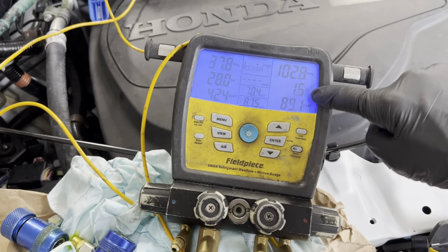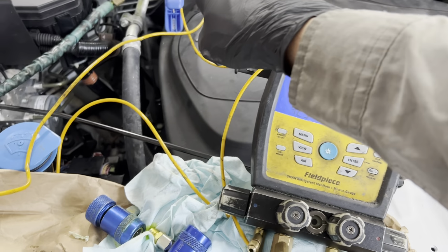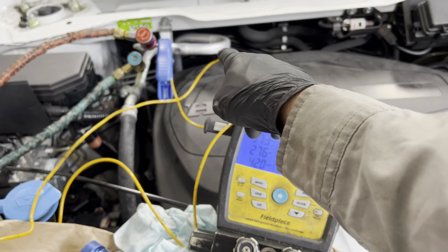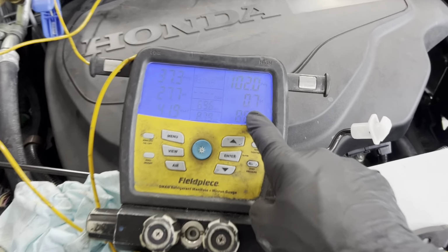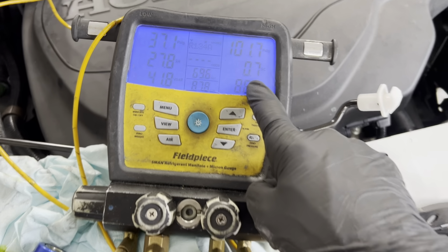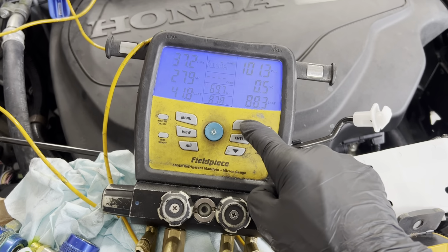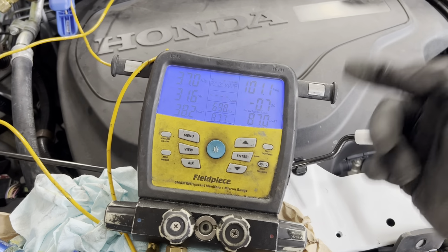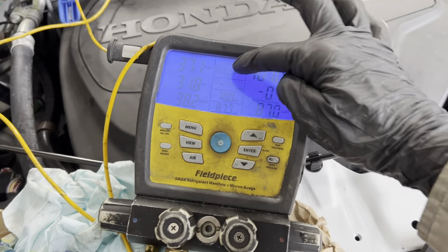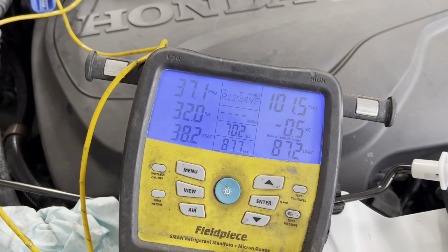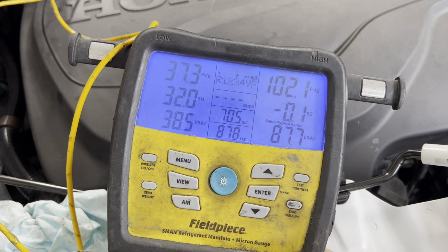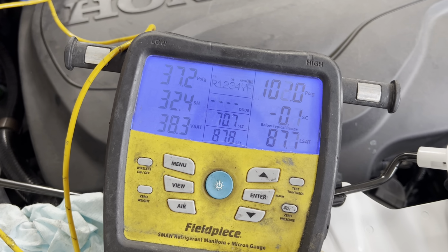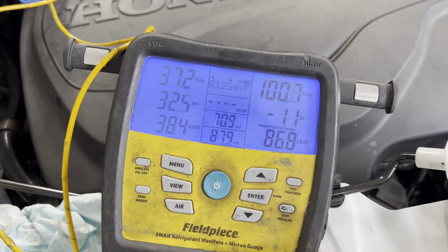Look at what our subcooling is. At that point, that's where it enters out of the condenser right here. So by the time it gets to the internal heat exchanger, look at where our subcooling is. Oh, yeah, idiot. Okay, now look at where our subcooling is. Now we got the right gas. It was on 134. This is a YF vehicle. Little difference. We're at near zero superheat, subcooling.